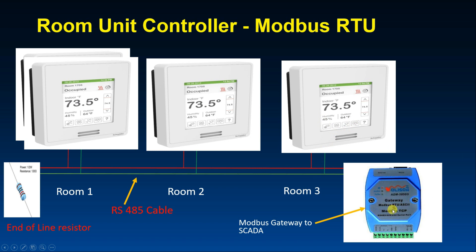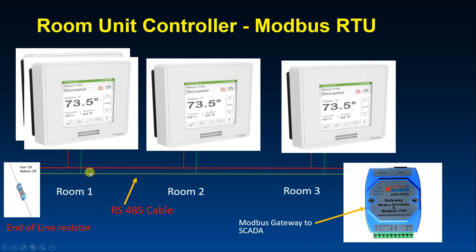Why use a Modbus gateway? It takes the information from the RTU devices and passes it to Modbus TCP via a LAN Ethernet cable, which goes to our SCADA or PLC so we can control all the fan coils from a central location. Also note that we have a termination resistor on the communication line for impedance matching, ensuring data is transmitted and received properly by the gateway.